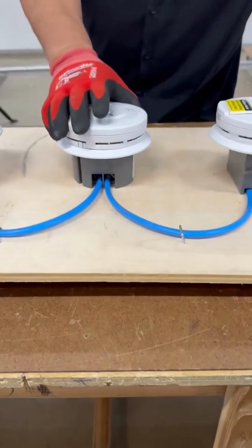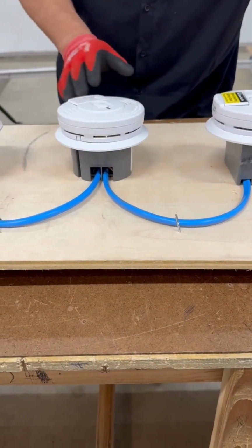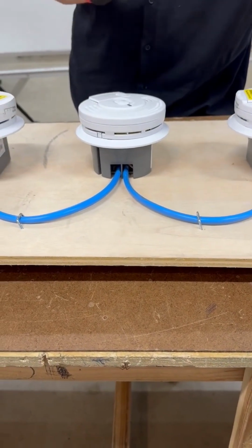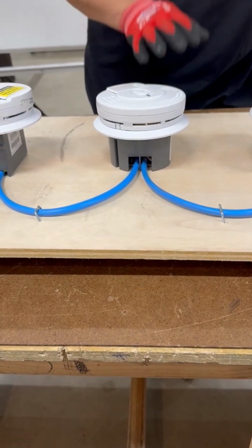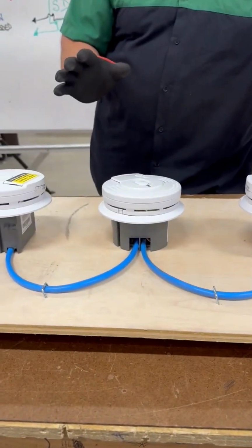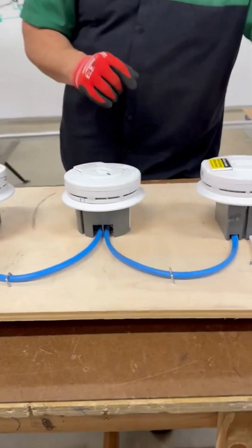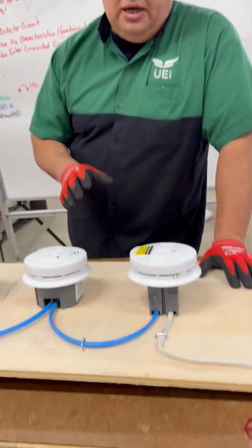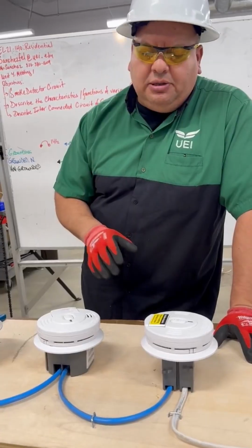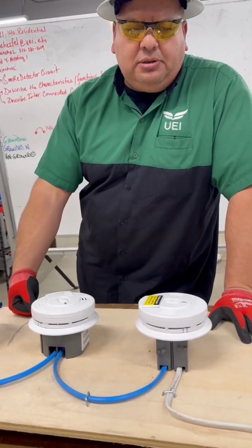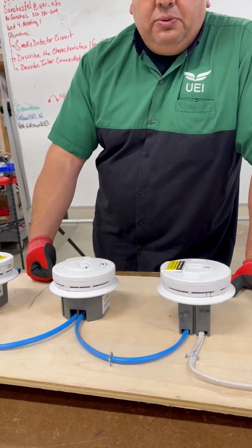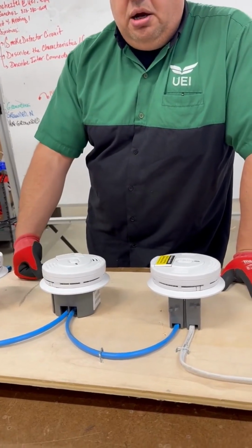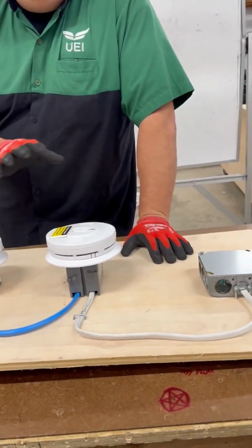One of the other things that people should expect is anytime that the circuit is de-energized, meaning we lost power to our circuit, the alarm system should alarm. It should alarm. And that's a manufacturer kind of detail that usually happens. Let's try it out. Let's see if it happens. Okay, we didn't get it, right? We just cut off power here. We didn't get the alarm. But that's a manufacturer detail.